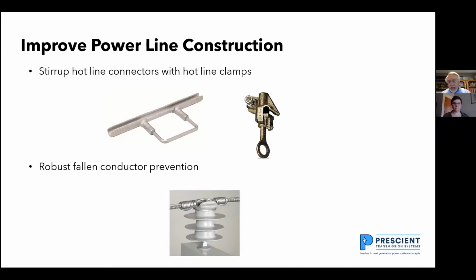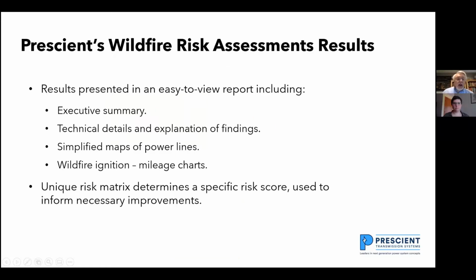And when I get to areas where wildfires are a risk, I should be using robust falling conductor prevention, which basically means what I want to do is harden all my connections so that I don't get a falling conductor. A conductor doesn't fall off in the wind and doesn't ignite a wildfire. So I'm looking at enhanced protection, enhanced power line construction.